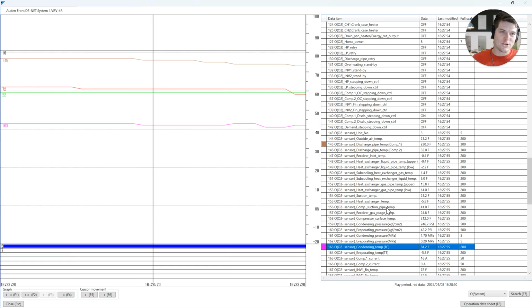Saturation. Why does saturation matter? Because this is refrigeration and we need to know what it is. Is it a liquid or is it a vapor? The way we find that out: if it's below my saturation temp, guess what, guys? It's a liquid. Woohoo! There's some confetti for you. If it's above my saturation temperature, guess what it is? It's a superheat. Have some more confetti. Congratulations, we just covered the basics of AC and refrigeration.